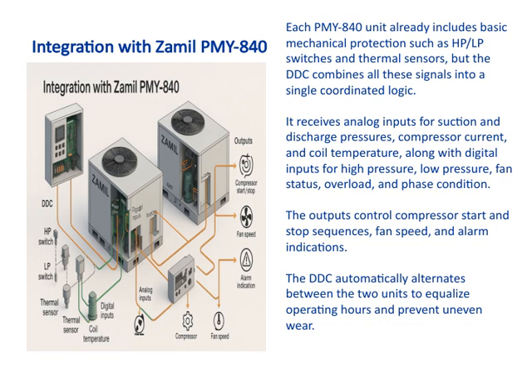Each PMY-840 unit already includes essential mechanical protections, such as high and low pressure switches and thermal sensors, which are crucial for safeguarding the system. However, the real advantage comes from the DDC, or Direct Digital Controller, which consolidates all these signals into a single, coordinated logic system. This means it receives a variety of inputs: analog inputs like suction and discharge pressures, compressor current, and coil temperature, as well as digital inputs such as high pressure, low pressure, fan status, overload, and phase condition. By gathering all this data, the DDC can make smarter, real-time decisions to control the system more effectively.